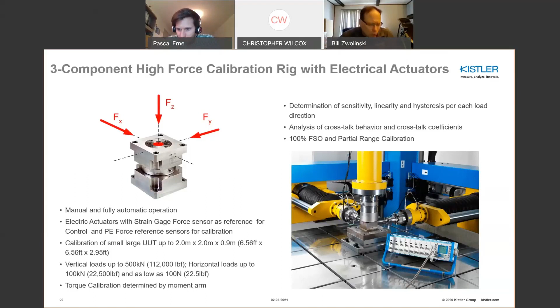And in terms of any dynamometer, this isn't a practical way of doing it in a force limiting test, but force dynamometers are often calibrated with multi-component presses, with electric actuators, with strain gauge force sensors for reference, and PE force reference sensors for calibration. So you have the ability to apply very precise forces at known loads and be able to calibrate the entire system, which is obviously not so practical in a force limiting test. So we're going to talk about what we do in those situations in the next few slides as well.